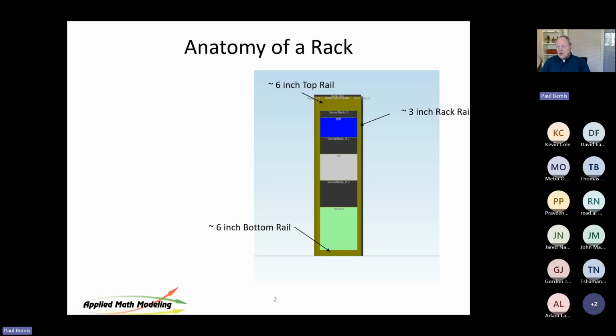So what you want to model is the rail. You want to model the leakage around this. I'm assuming that the customer, your customer, or if you're doing this yourself, your servers have blanking panels in it. That's what this is. The black is a blanking panel. So if there's no equipment in the slot, there needs to be a blanking panel there. If not, start there. It doesn't have to be complicated. You can use cardboard. I've seen that done. In fact, they have some cardboard that's not flammable that you can use magnets and just stick them in. I mean, blanking panels can be expensive because there's a lot of them.